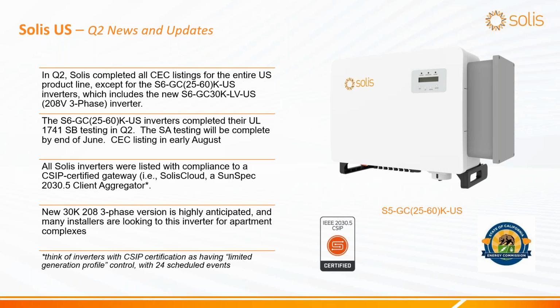What does that mean? The new SB capabilities meeting IEEE 1547-2018 are capable of grid interoperability with a limited generation profile control. But with CSIP certification, you're able to accept up to 24 scheduled events over the course of the day. So as far as Solis is concerned, having CSIP certification is beneficial to customers in the long run.